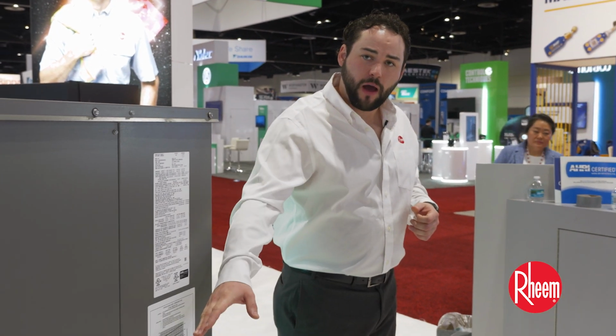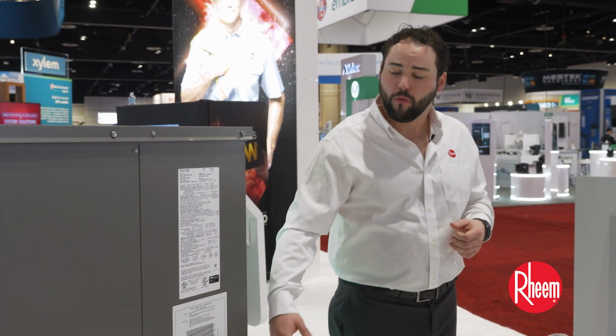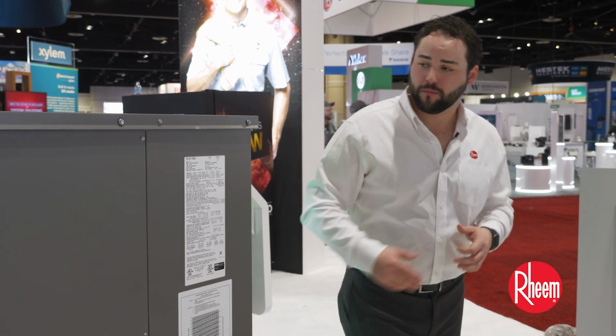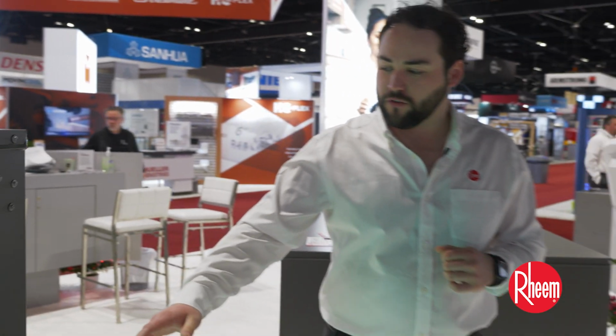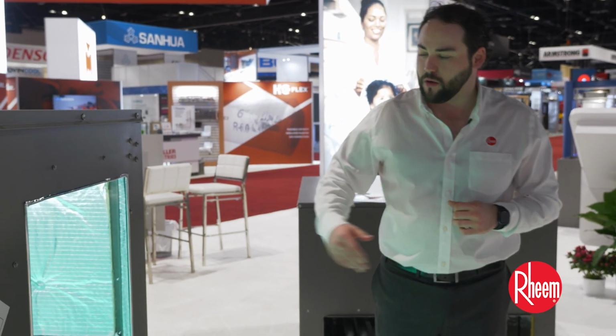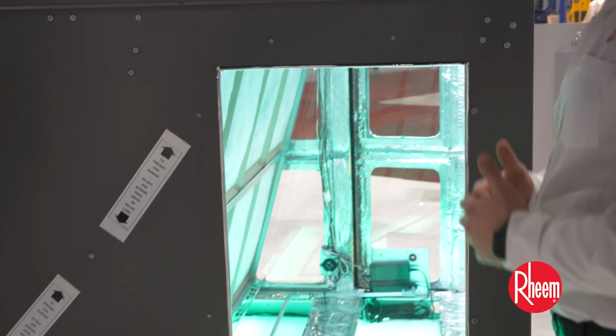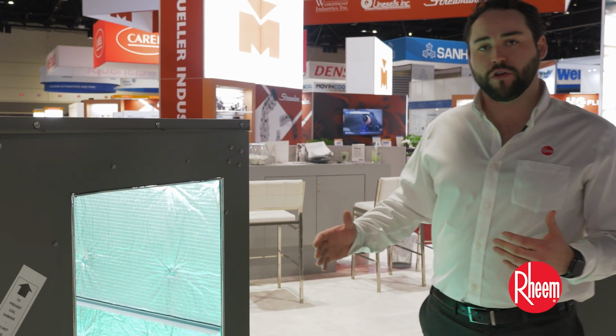Moving over here to the other side of the unit, this is where our economizer would be installed if applicable with our barometric relief dampers. Here in the other side of the return section, what you will notice within the unit is that we utilize A2L refrigerant sensors. This is of course required by code now with the new refrigerant change. We utilize 2 in our larger units and only 1 in our smaller units.